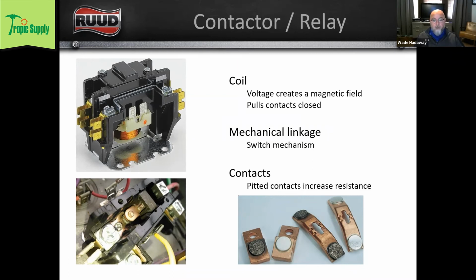As contacts open and close repeatedly, they can become pitted. And if you look at the graphic on the bottom, you can see a pitted set of contacts and a nice new clean set of contacts. So as those contacts open and close, there's often a little arc that draws there. Anytime that arc is drawn across those contacts, it causes some pitting. And as those contacts become pitted, they have a higher resistance, meaning that it makes it harder for the power to get through. So when you're out and you're doing your maintenance, check voltage across your set of contacts on your contactor. You shouldn't really have a voltage drop across it. I mean, you might see 1 volt or a portion of a volt. But best case scenario, you really don't want to see any lost voltage across your set of contacts.